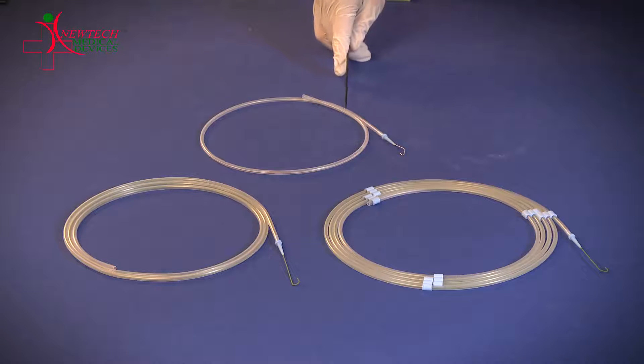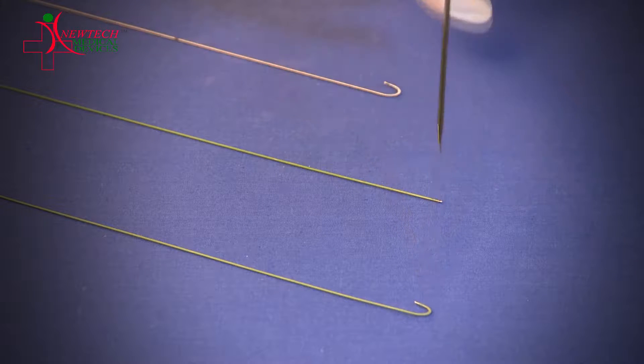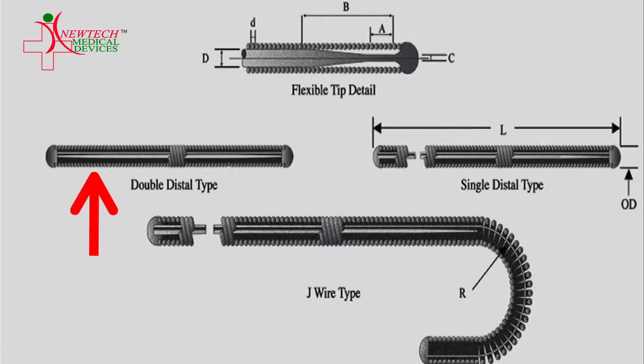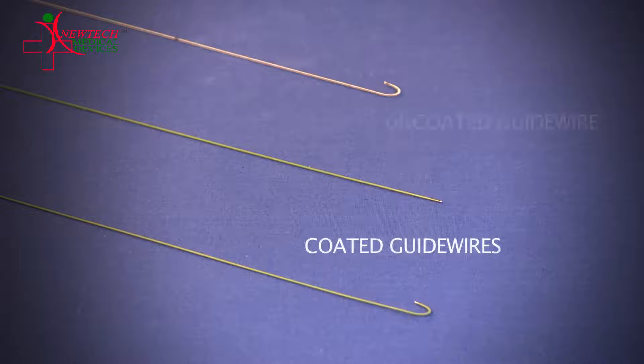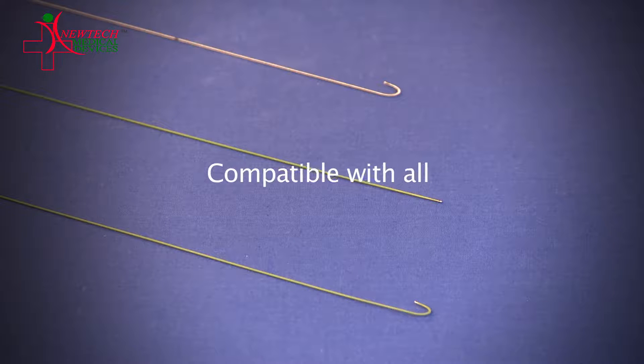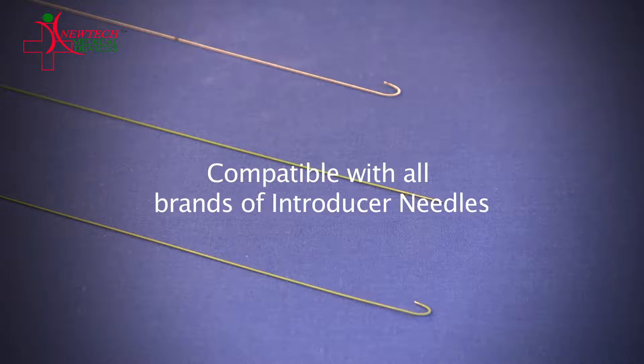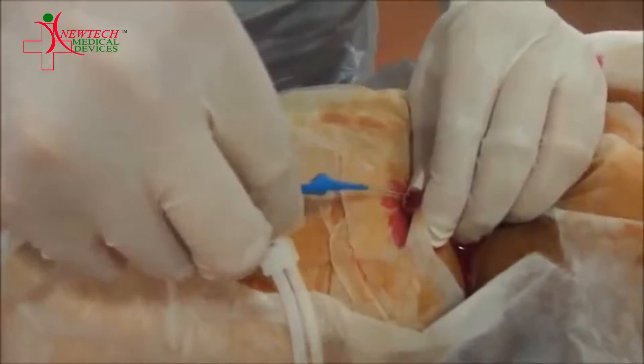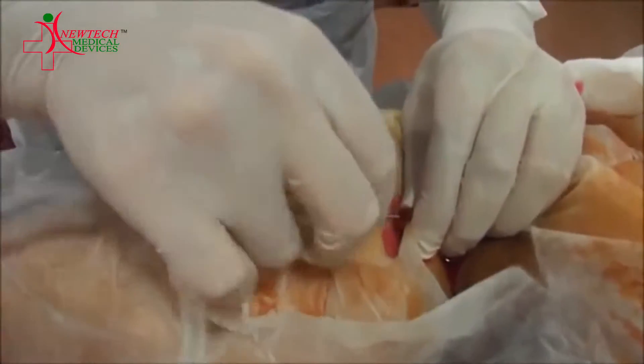The diameter of the guide wire can vary from 0.018 inches to 0.038 inches. This is a dialysis guide wire with a J-tip. We can also provide the same in straight tip, and in single and double distal form. A single distal guide wire is stiff at one end and flexible at the other, while a double distal is flexible at both ends. Though we offer coated and uncoated guide wires, an uncoated guide wire is usually used during the hemodialysis process. Our guide wires are compatible with all introducer needles available in the market.